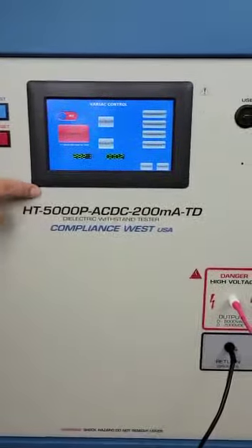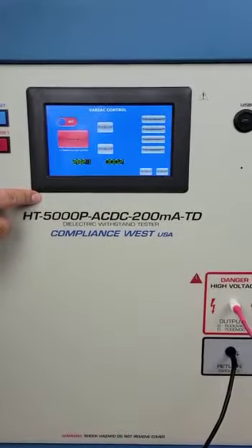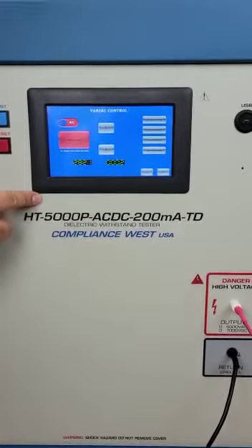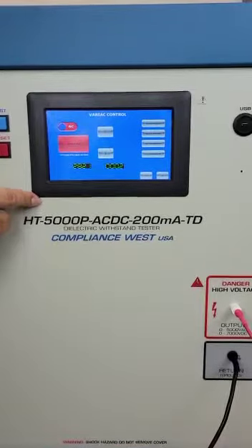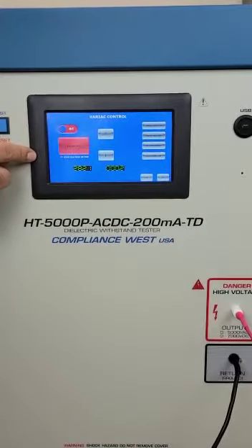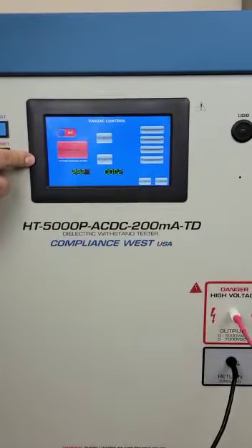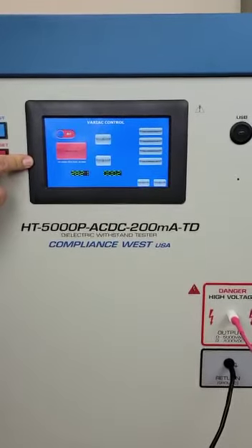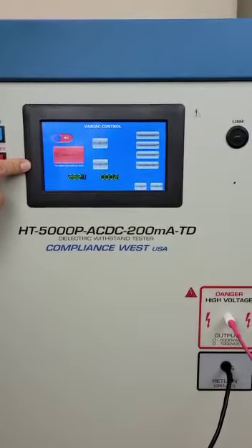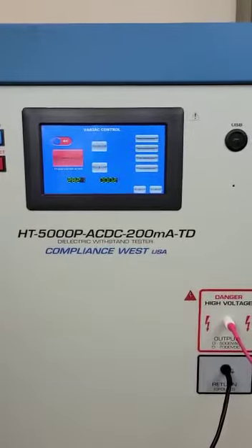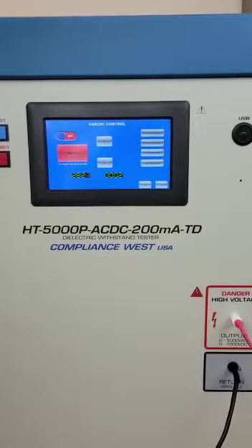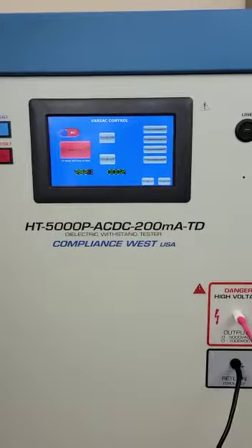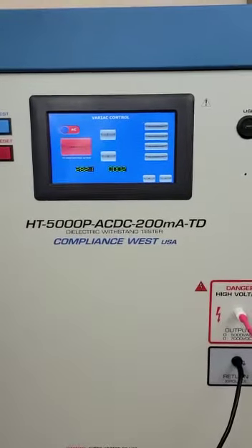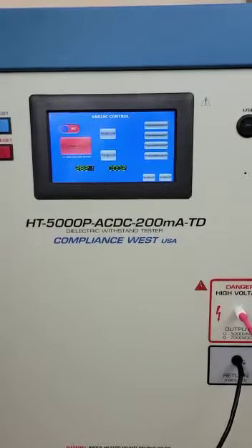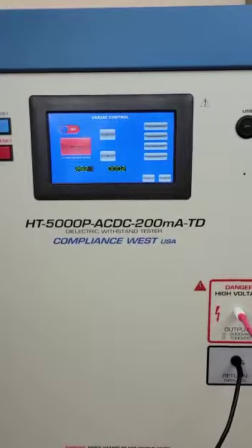In this screen, we can see we are set to calibrate the AC voltage. We have a red button to enable the high voltage, and on the right side, calibration voltage high and calibration voltage low. That button is going to be pressed to indicate which value we are calibrating. We're going to press test.